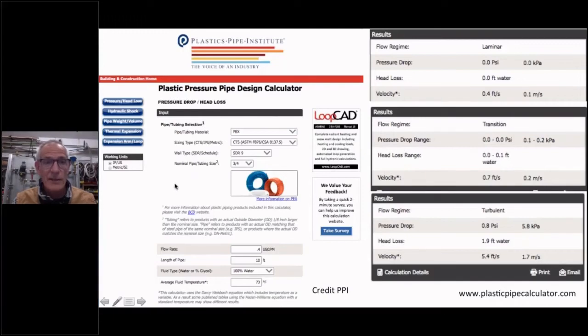So most of the other piping materials out there, whether it's copper pipe, you can find a chart like this online. You can find one for steel pipe, Schedule 40, Schedule 80. One of the best resources I found for looking at other pipes is called the Engineering Toolbox. It's just a website that has all sorts of different calculators, and if you put in a flow velocity calculator, it will come up, and you can input the type of pipe you have, the flow rate, the size of the pipe, the type of fluid, the temperature. I mean, you can really nail it down to a tight number.